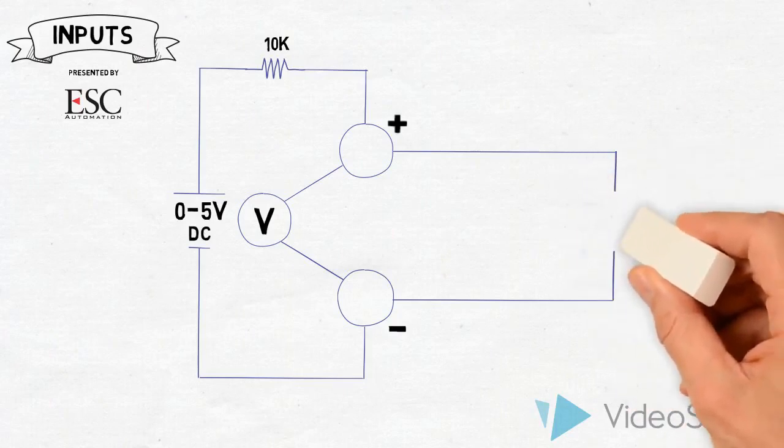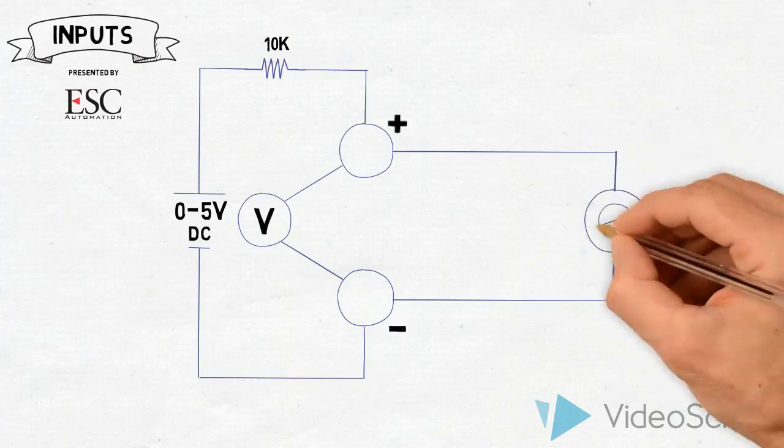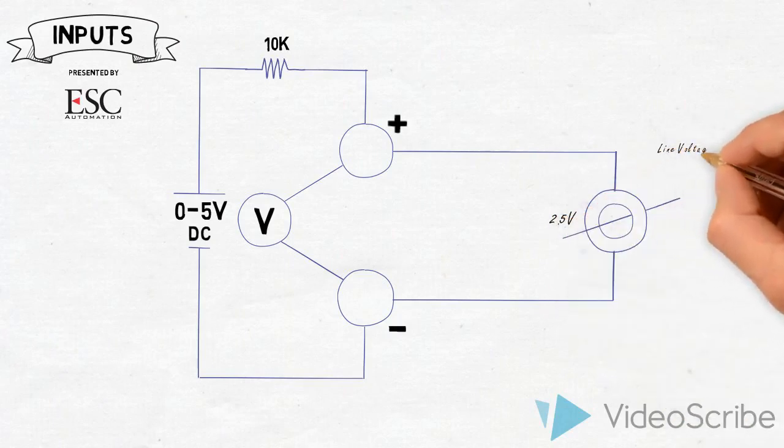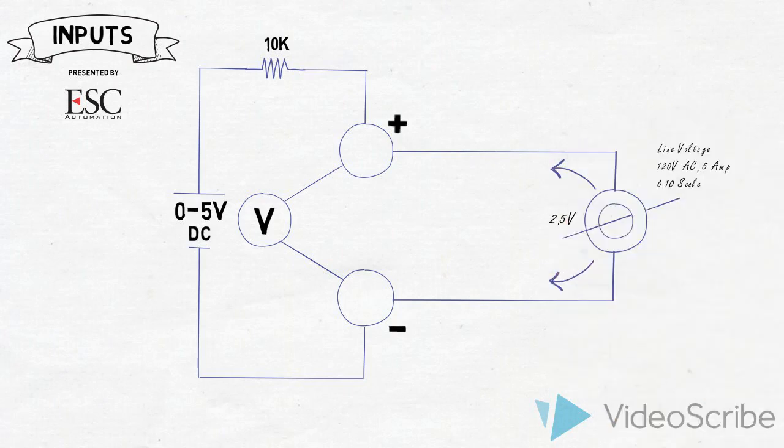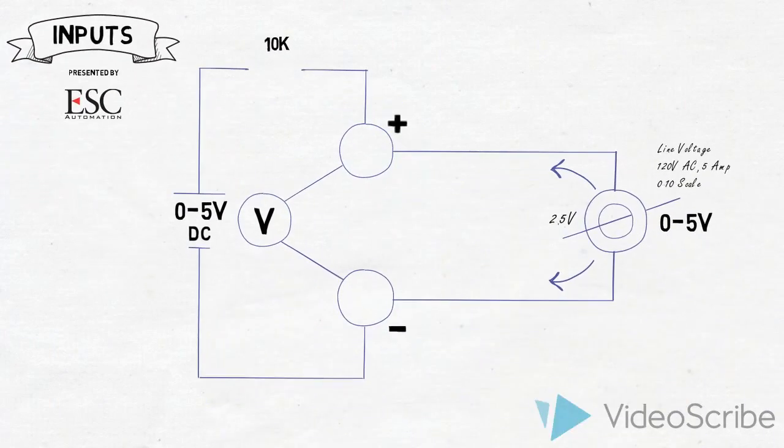The next input is a current sensor—a donut that wraps around a line voltage. The current sensor provides a voltage to the panel, zero to five volts. When we set the dip switch on the panel, the resistor gets pulled out and there's no power supply coming from the panel. Now the voltmeter reads the voltage from the actual device, not from the panel's power supply. We convert zero to five volts from the device to amps.